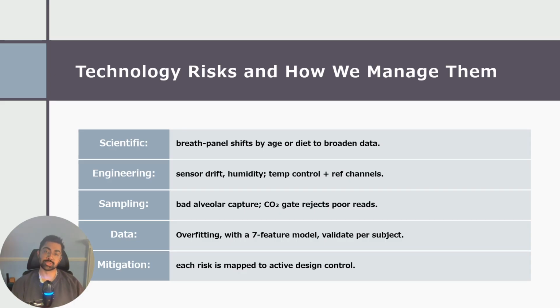Biological variation across age, diet, and activity can shift breath profiles and thresholds. We mitigate variability by enlarging cohorts, stratifying models, and applying context-aware thresholds. Chemiresistor drift and humidity can also bias readings, so we add temperature control and reference channels. Sampling errors could degrade accuracy as well, so we enforce carbon dioxide gating, quality flags, and repeat read logic. Overfitting risk is contained by locking a small feature set and validating subject by subject.